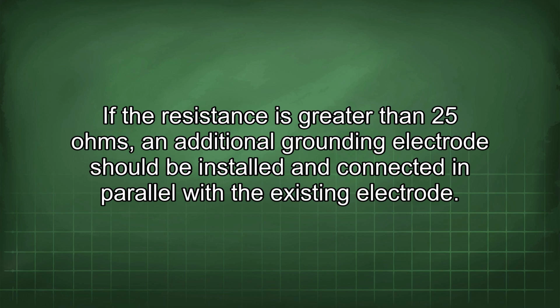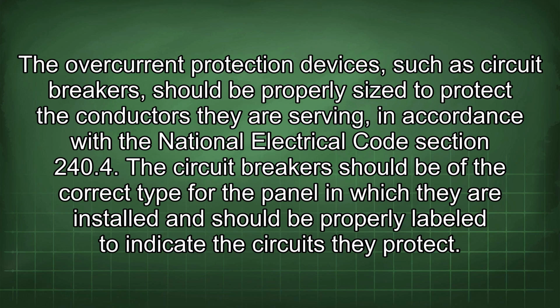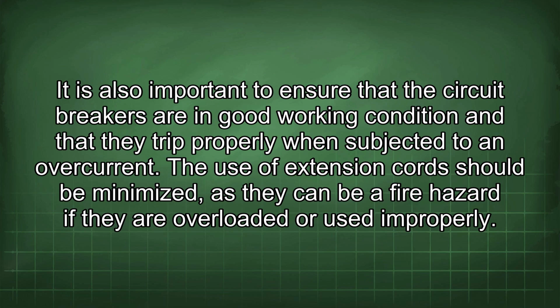The overcurrent protection devices, such as circuit breakers, should be properly sized to protect the conductors they are serving, in accordance with the National Electrical Code Section 240.4. The circuit breaker should be of the correct type for the panel in which they are installed and should be properly labeled to indicate the circuits they protect. It is also important to ensure that the circuit breakers are in good working condition and that they trip properly when subjected to an overcurrent.